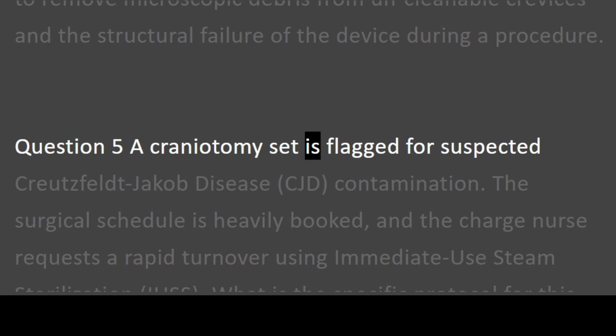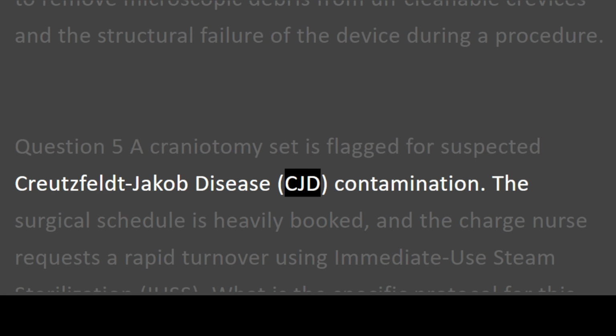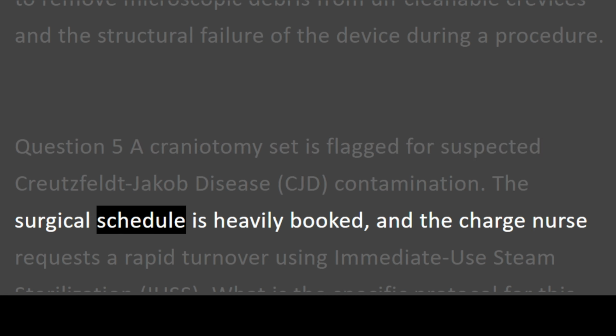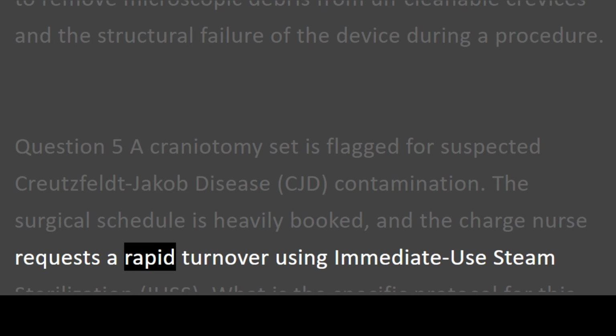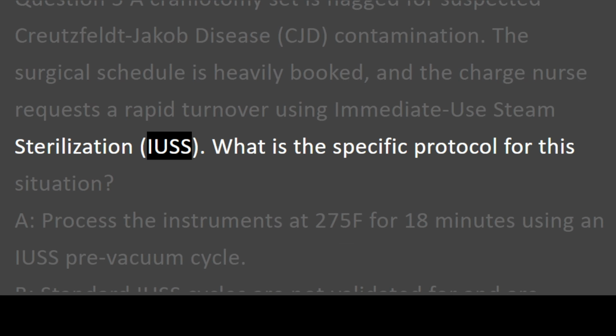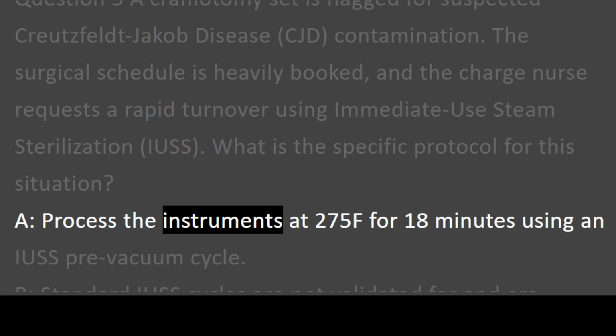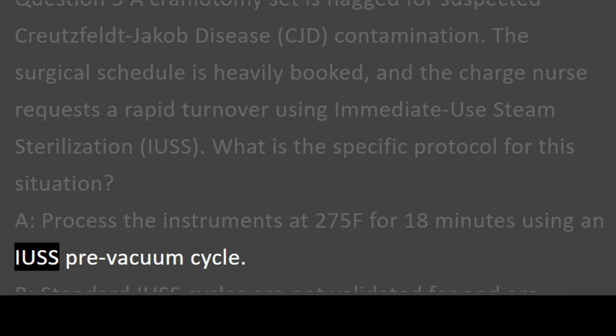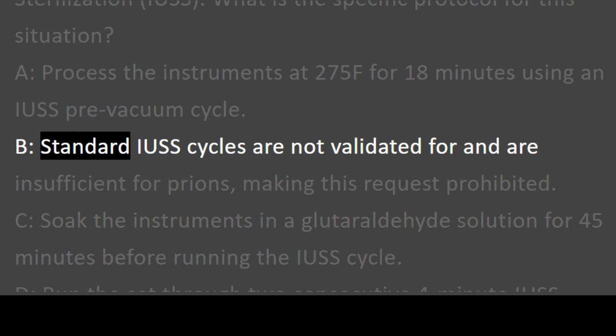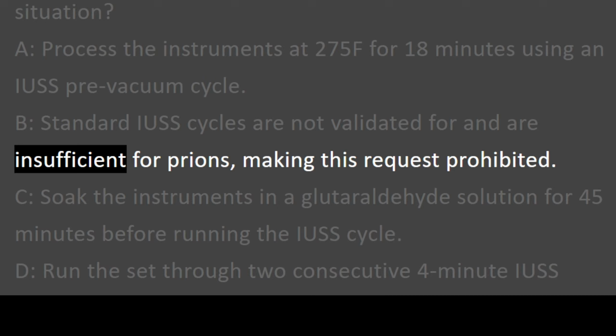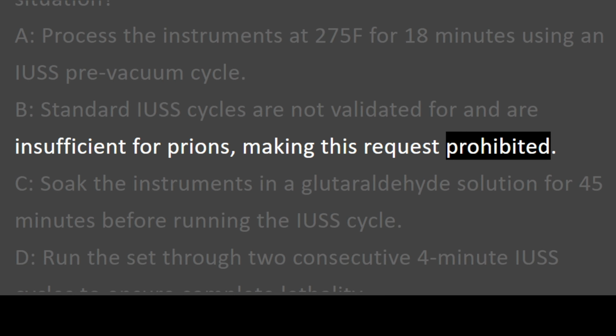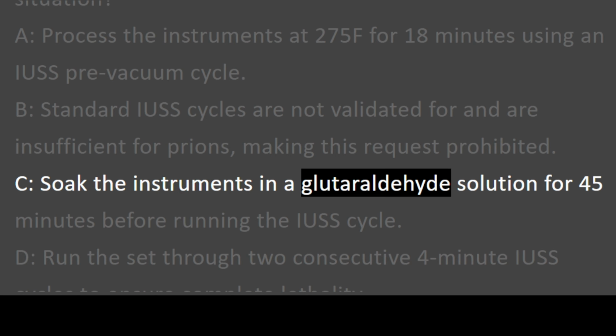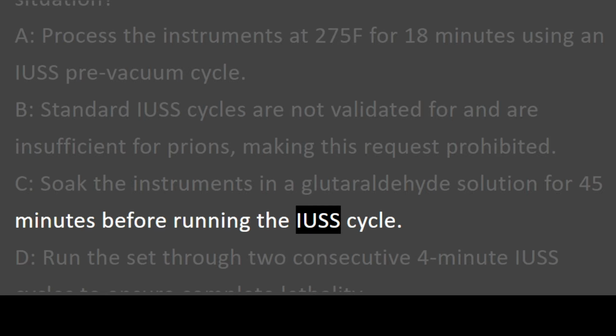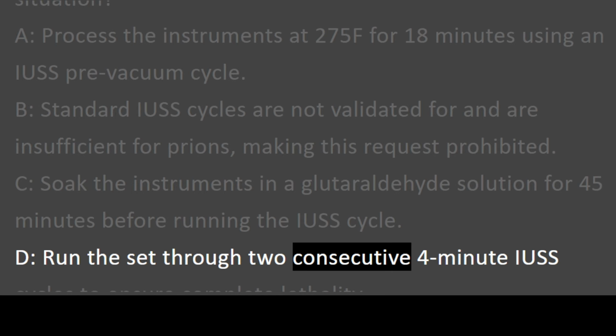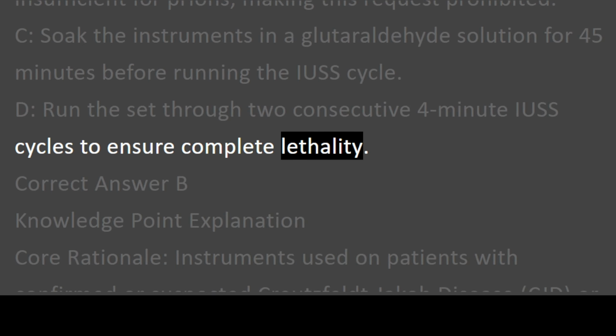Question 5A. Craniotomy set is flagged for suspected Creutzfeldt-Jakob disease, CJD, contamination. The surgical schedule is heavily booked, and the charge nurse requests a rapid turnover using immediate use steam sterilization, IUSS. What is the specific protocol for this situation? A. Process the instruments at 275 F for 18 minutes using an IUSS pre-vacuum cycle. B. Standard IUSS cycles are not validated for and are insufficient for prion, making this request prohibited. C. Soak the instruments in a glutaraldehyde solution for 45 minutes before running the IUSS cycle. D. Run the set through 2 consecutive 4-minute IUSS cycles to ensure complete lethality.